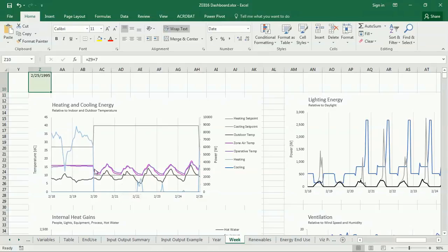And what's going on, it looks like, is that this is a weekend, and this is a week. These are the weekdays here. So remember, we just changed it for the weekdays, not for the weekends. So we are getting some energy use, and in fact, you can see this is the heating. So we're getting all of this heating energy, and then when the thermostat drops down, it drops way down. And it's very interesting to see that.